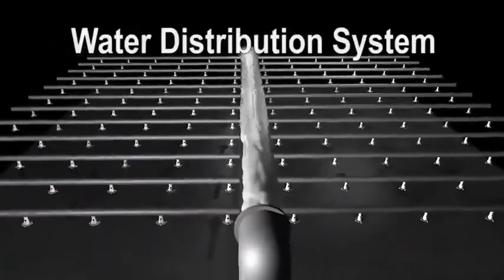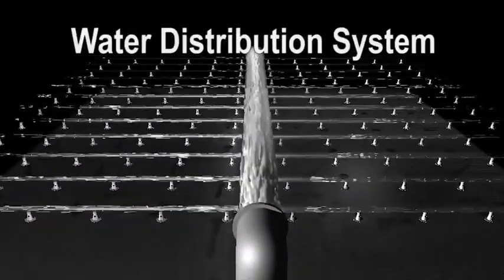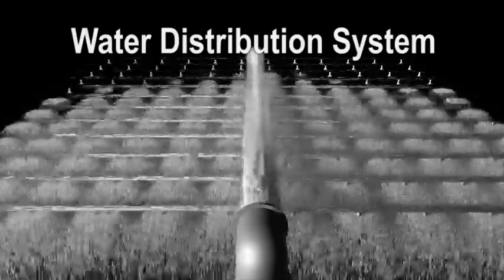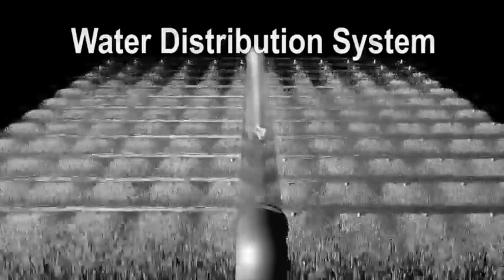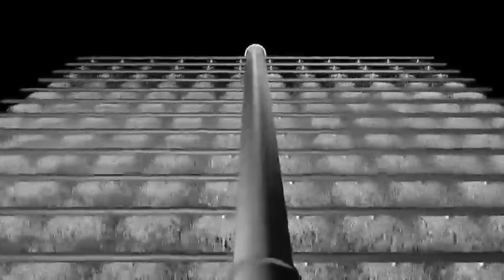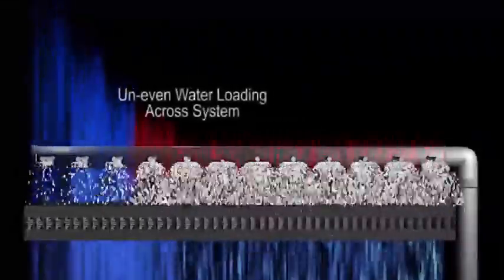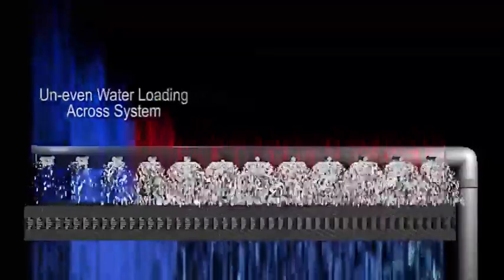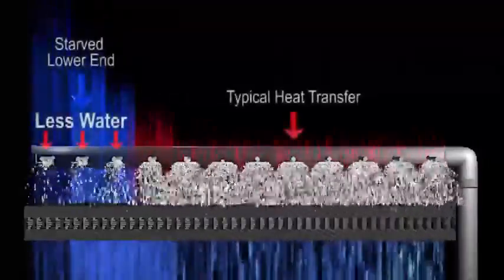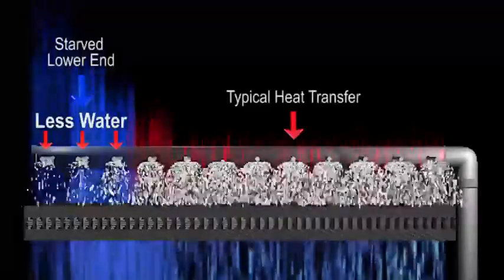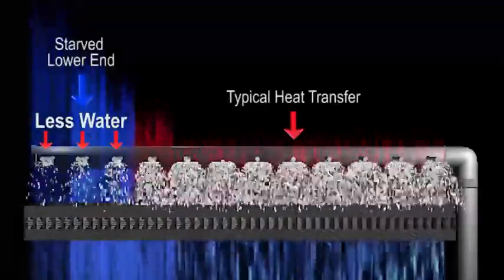When the counterflow tower distribution system was designed, the logic was to use the velocity pressure produced by the pump to create an equal static pressure at each nozzle, resulting in a balanced water loading over the film media. The common problem with water distribution systems today is the static pressure at the nozzle tends to bleed off before the velocity pressure in the piping can fully charge the system. The result is uneven water loading across the system, often starving the lower end of the distribution system of water. This results in a waste of both fan and pump energy.